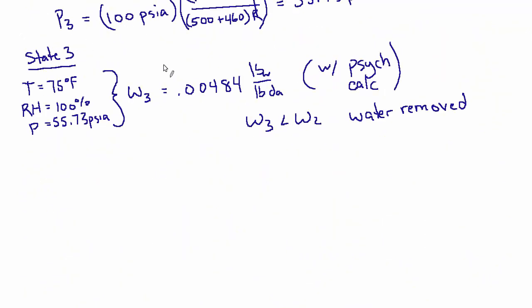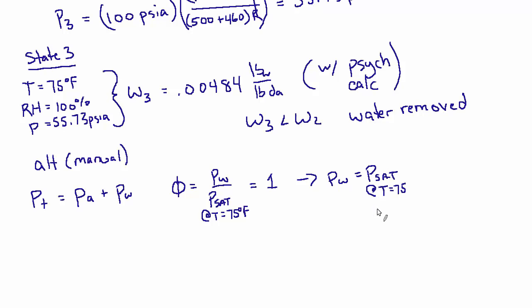But regardless, let's look at a manual alternative now, very similar to what we did in the previous part, where we find the humidity ratio for state three without using a psychrometric calculator. So again, we're going to want to get the partial pressures. So let's say the total pressure equals the partial pressure of the air plus the partial pressure of the water vapor. And the humidity is the partial pressure of water vapor divided by PSAT at the temperature, which in this case is 75 degrees Fahrenheit. Well, we know the relative humidity is 100%. So this ratio equals one. So that means then that the partial pressure of water vapor equals the saturation pressure at that temperature because the air is saturated.